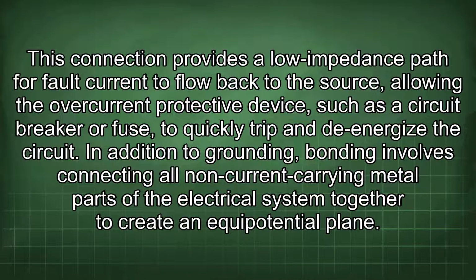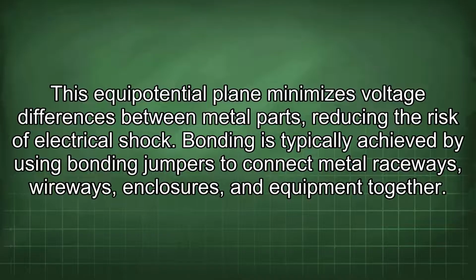This connection provides a low impedance path for fault current to flow back to the source, allowing the overcurrent protective device, such as a circuit breaker or fuse, to quickly trip and de-energize the circuit. In addition to grounding, bonding involves connecting all non-current carrying metal parts of the electrical system together to create an equipotential plane. This equipotential plane minimizes voltage differences between metal parts, reducing the risk of electrical shock. Bonding is typically achieved by using bonding jumpers to connect metal raceways, wireways, enclosures, and equipment together.